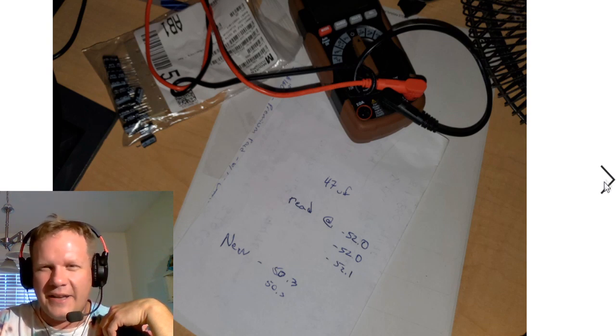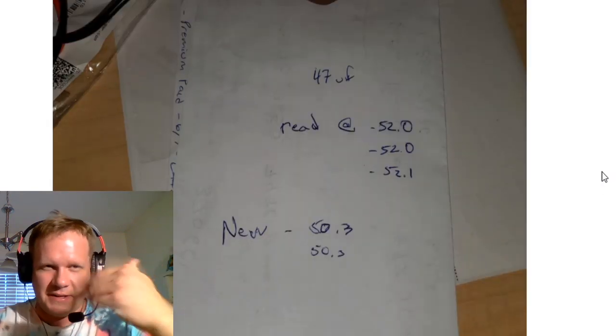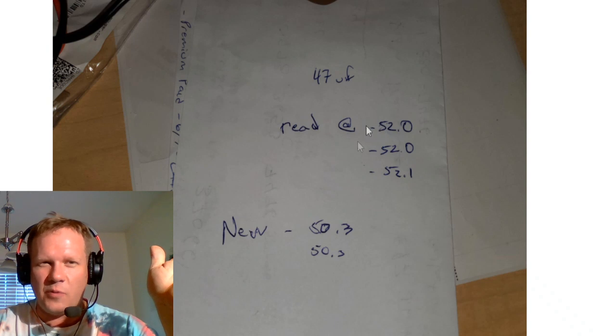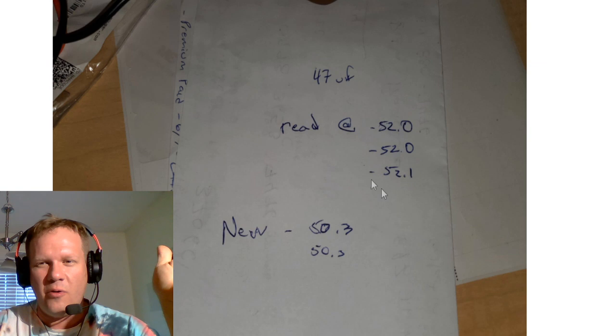I took some readings, which I've got listed here. This was the capacitor I pulled, and it kept reading at 52.0, 52.1, or higher. So it wasn't going down; it was actually reading higher than the 47 microfarads it should be, out of spec by at least a little over 10%.